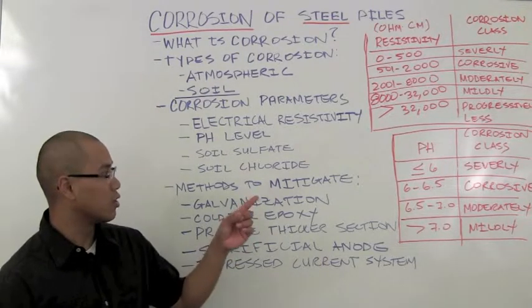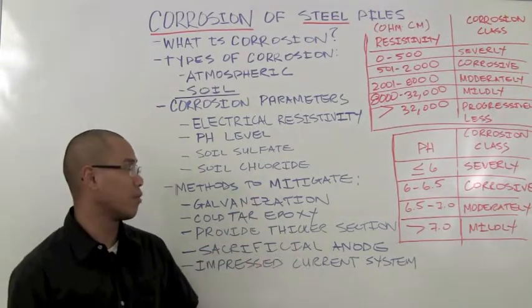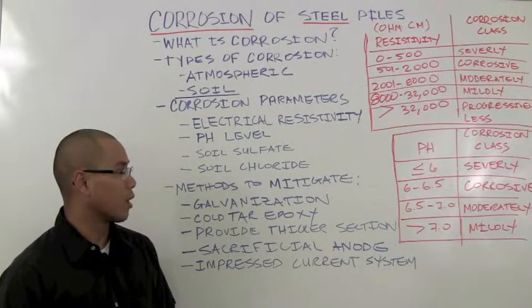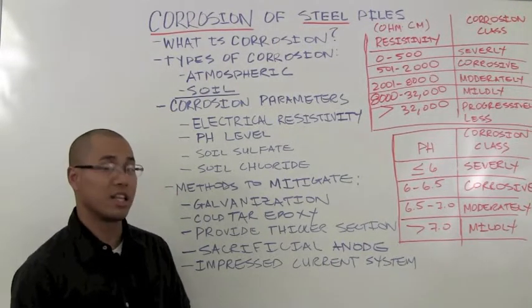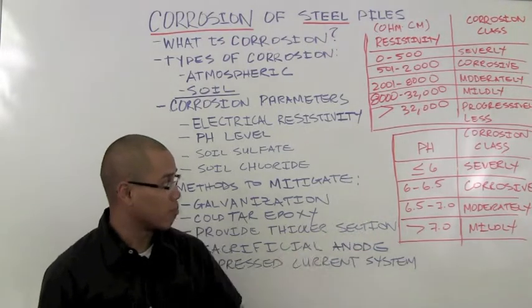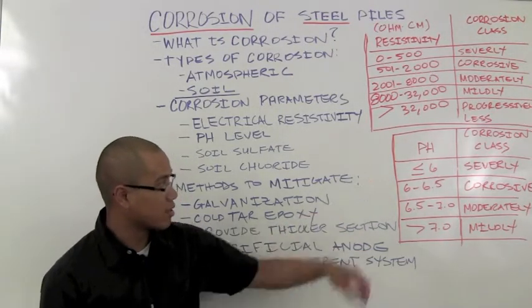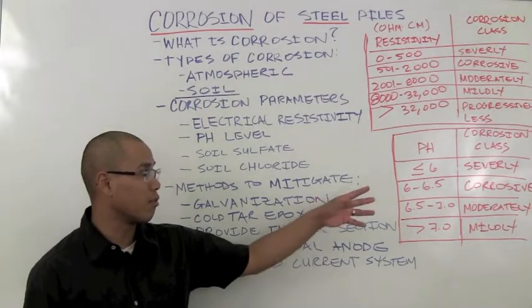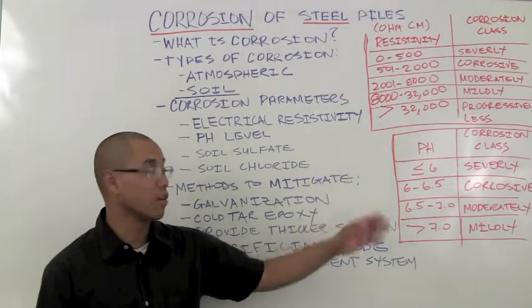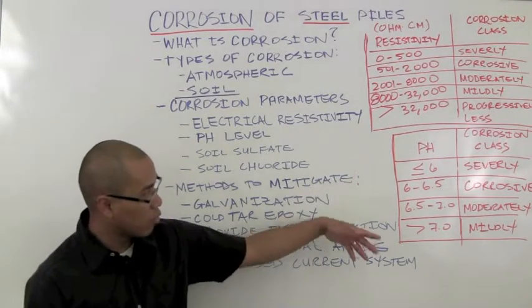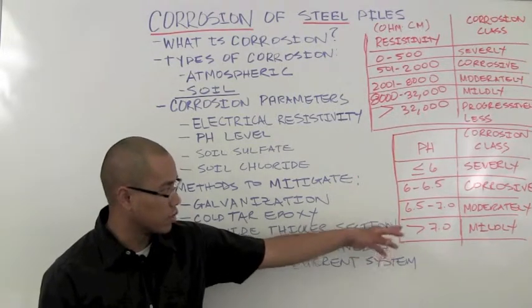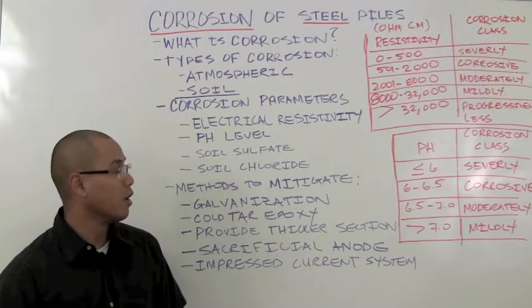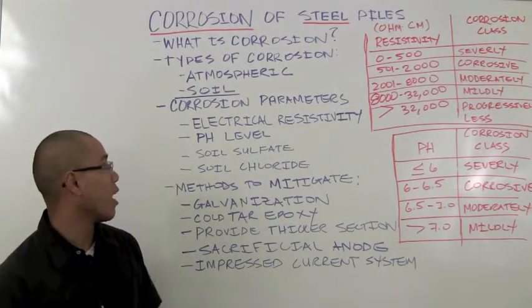Extremely low pH levels tend to accelerate the corrosion of the zinc plating. As you can see in the table, anything less than a pH of 6 is classified as severely corrosive. As you approach near neutral soils, which is above pH 7, you get mildly corrosive conditions for steel piles.